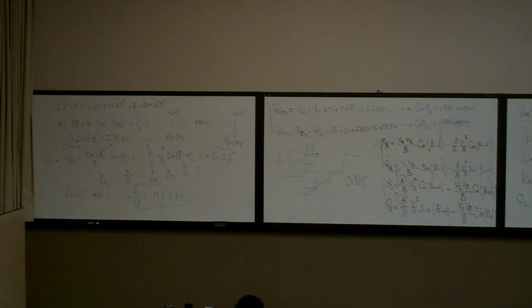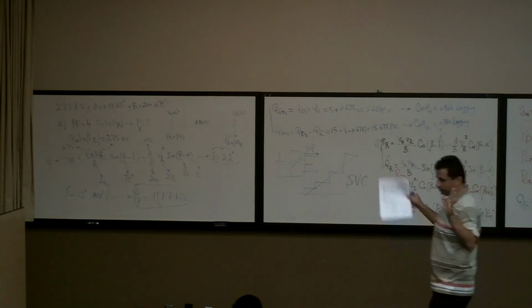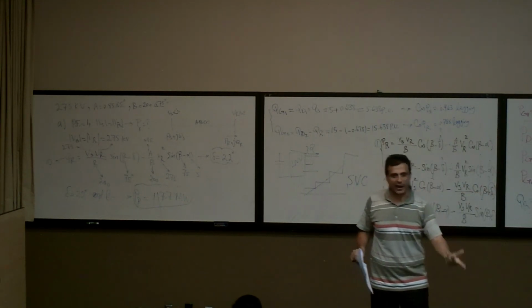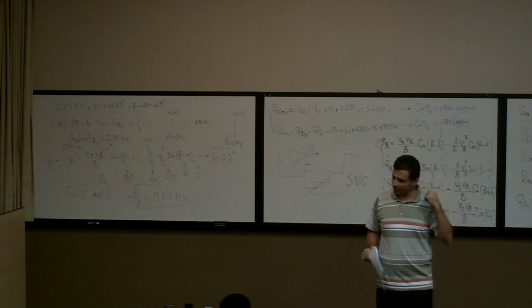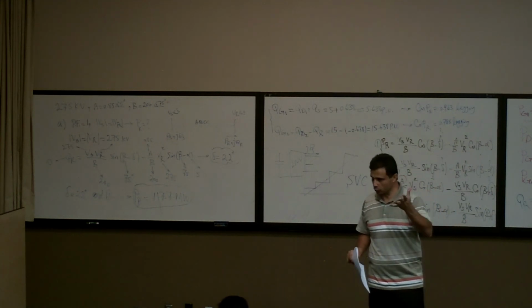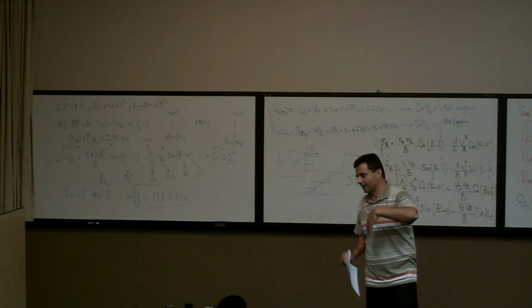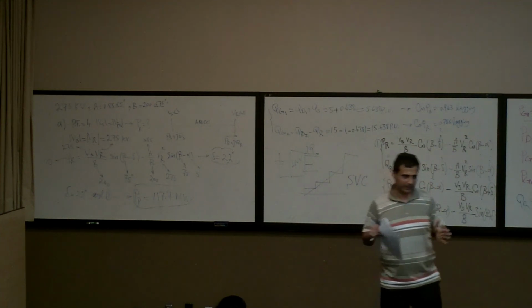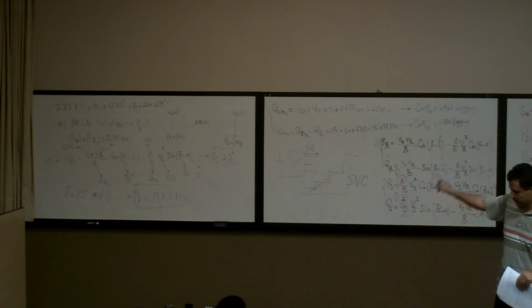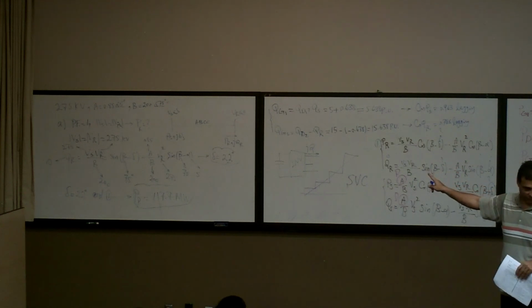So now going back to this example. From the previous example, we found out that if we want to keep the voltage profile flat, we have to inject reactive power. In the previous example, generator number 2 did that, injecting reactive power into the bus to keep the voltage constant. In this case, we don't have a generator.